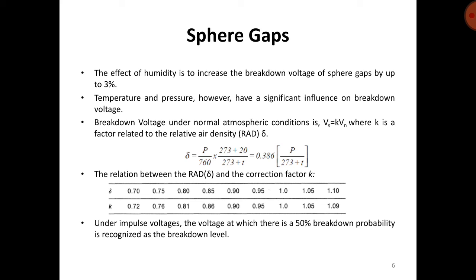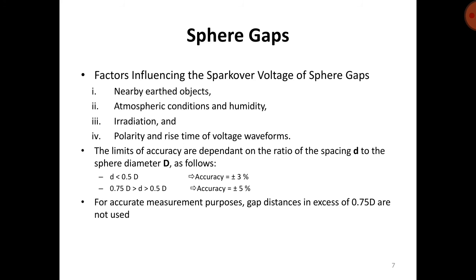Under impulse voltages, the voltage at which there is a 50% breakdown probability is recognized as the breakdown level. Now, what are the factors that influence the spark over voltage of sphere gaps? These are nearby earthed objects, atmospheric conditions and humidity, irradiation, and polarity and rise time of voltage waveforms. So these are the factors that influence the measurement of sphere gaps.